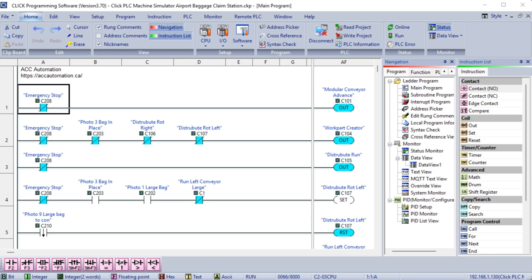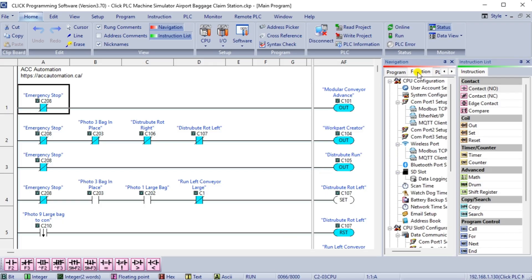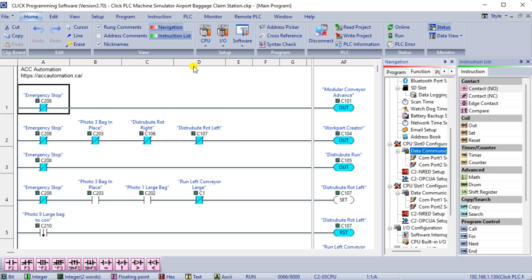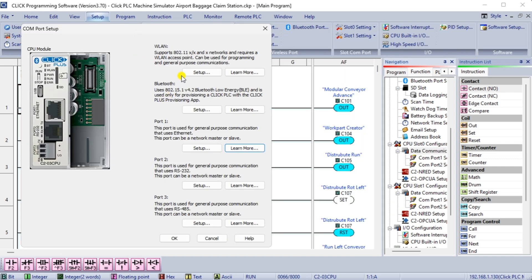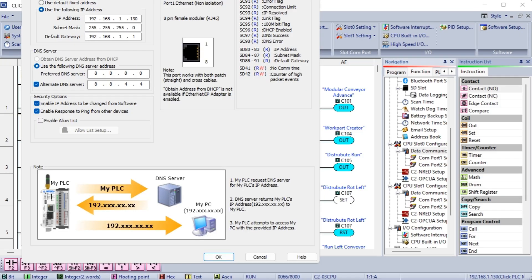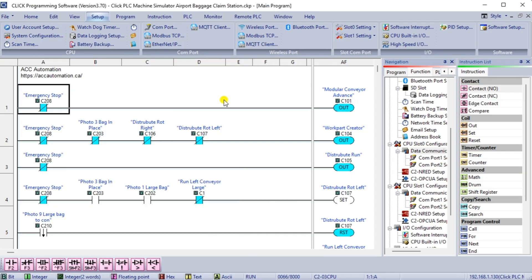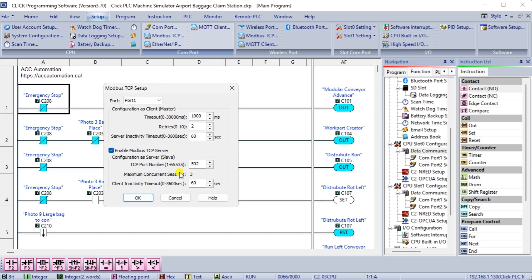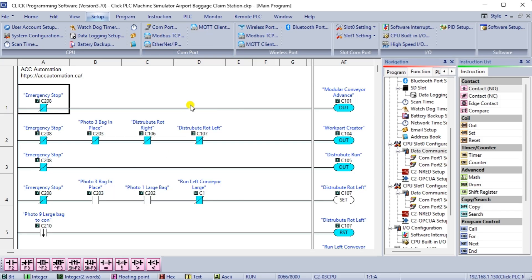We communicate with the machine simulator using Modbus TCP Ethernet or wireless. The ports will be set up with a fixed IP address so the machine simulator Modbus client can find the Modbus server. Select Modbus TCP from the communication port on the function tab of the navigation window. You can also use the main menu bar setup bar com port. Click on the setup button for port 1. You can now set the static IP address on the com port setup details window — make a note of the IP address, as we will need this to connect to our machine simulator. Select Modbus TCP setup from the main menu, and ensure the enable Modbus TCP server is checked for our port. Ensure that the PLC is in run mode. Select status to see the active status of the inputs and outputs on the ladder logic.